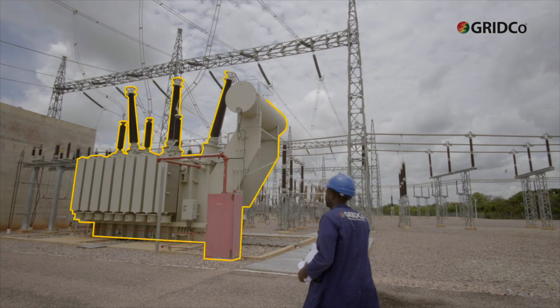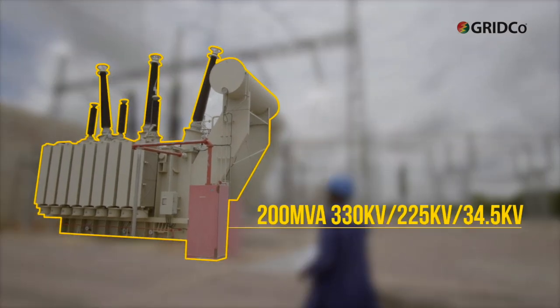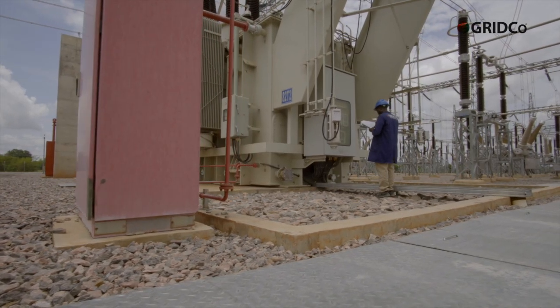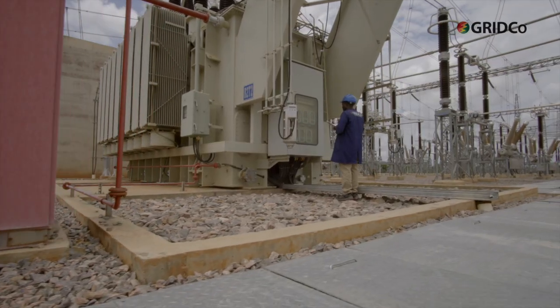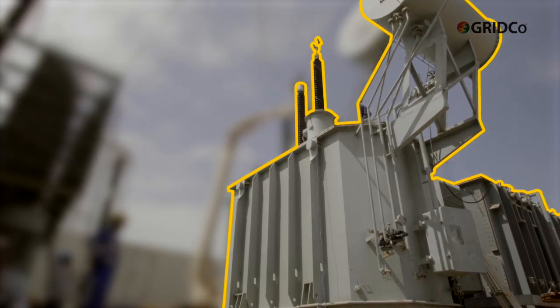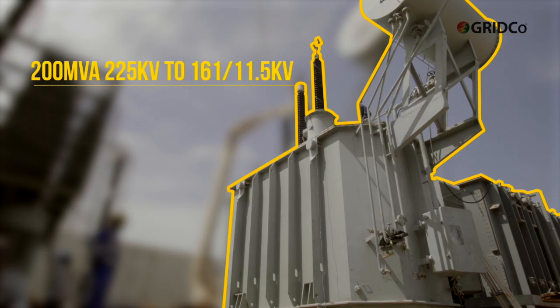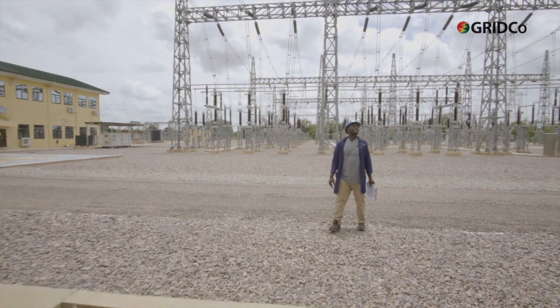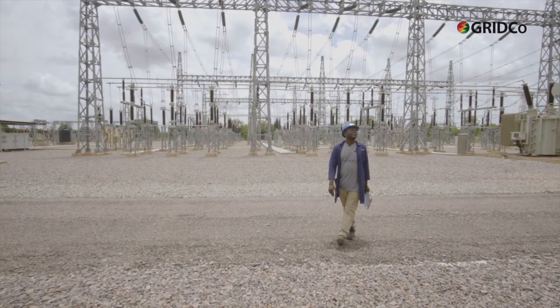The defective transformer was a 200 MVA 330 kV / 225 kV / 34.5 kV step-down auto transformer. The customer, Sonabel in Burkina Faso, needs a transmission voltage of 225 kV. The new transformer installed is a 200 MVA 225 kV to 161 to 11.5 kV step-down transformer. We will now use one of the 330 kV to 161 kV sino-hydro transformers, the one that interconnects into the 161 kV network of GRIDCo.